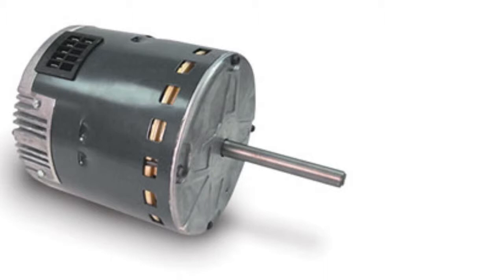There are several things that are different about the CTM. First, it is a one-piece motor with the electronics built into the back of the motor. It is a little bit longer than a standard PSC motor, but more compact than the variable speed. It is programmed for constant torque instead of constant volume and does not adjust for changes in static pressure. It also does not ramp up and down like the variable speed.